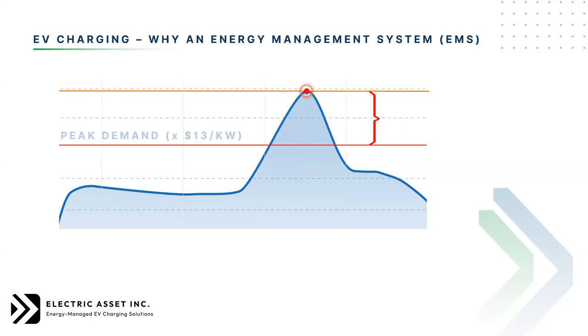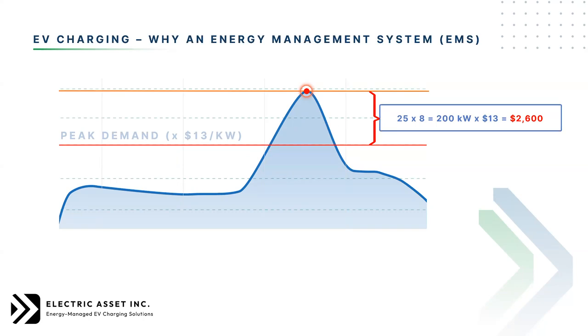So this event, happening once with 25 EVs plugging in at the same time, will drive an extra 200 kilowatts of peak demand - and this is over and above the energy actually used to charge the vehicle. This is the impact on the peak demand of the building. So 200 kilowatts times $13 is $2,600.